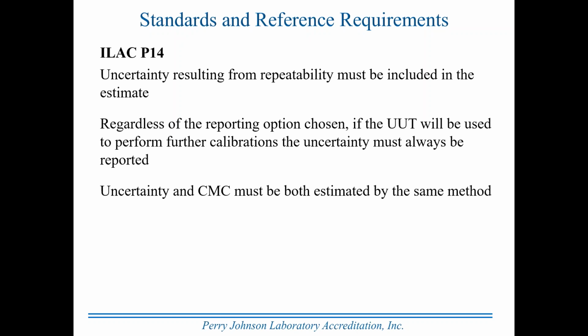And you're going to have a very good piece of equipment you're calibrating, but in all likelihood, it's not the very best in the world. So the estimate of CMC takes into account the performance of the best existing device, best in class. And so it is an estimate of uncertainty, but it's hypothetical in that the conditions under which it's estimated rarely actually exist. You may get very close to them, but not quite there.